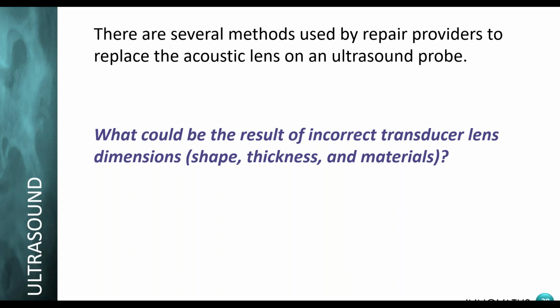If you put the lens of a transducer on too thin, that transducer will put out more power than the OEM intended. And when you do repair, you have to go back to OEM design and intent. You cannot improve the OEM design unless you're filing your own 510K. We're not regulated, but we should do it exactly the way the OEM did it. If you put on too thin a lens, you're putting out too much power. If you put on too thick a lens, you're not putting out enough power. It's like the scenario where I was scanning my thyroid and wasn't seeing any blood flow. I had perfectly fine blood flow. It's just that Acme Ultrasound put on a really thick lens and it was killing the acoustic intensity going into my body, so I wasn't picking up all that sensitive blood flow.